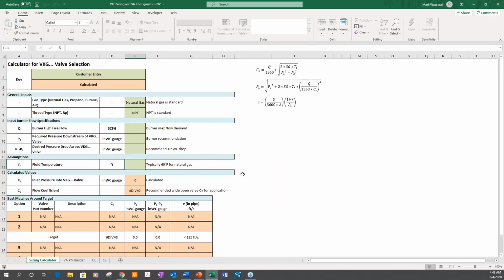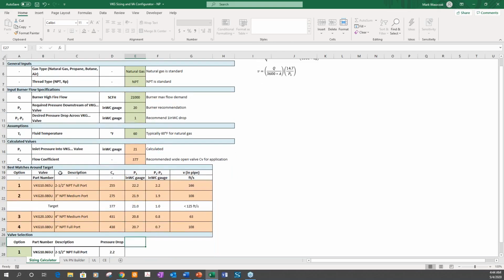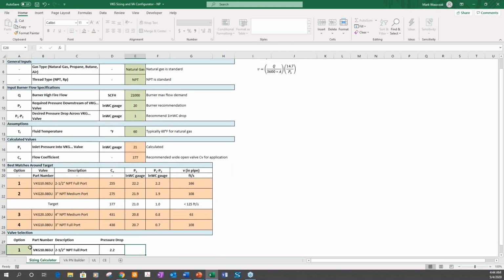Now, this program allows you to go in, and based on some information you input, it will select the valve size for you. So in our case, we're going to use a burner high fire flow of 21,000. Our manifold pressure, which is the downstream pressure of the VKG valve, will be 20 inches. We're going to use the recommended 1-inch pressure drop, and the recommended 60 degrees Fahrenheit for natural gas. So what this does now is it gives you 4 options. And at the bottom here, it gives you the option that is closest, I guess, to the target. In this case, it's a 2.5-inch NPT full port valve.